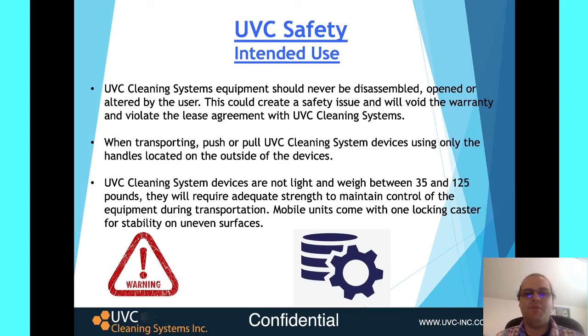UVC cleaning systems equipment should never be disassembled, opened, or altered by the user. This could cause a safety issue and will void the warranty and violate the lease agreement of UVC cleaning systems products. When transporting, push or pull UVC cleaning systems with only the handles located on the outside of the devices. And always remember that a lot of our devices weigh between 35 and 125 pounds, and they will require adequate strength to maintain control of the equipment during transportation. Our mobile units do come with a caster with locking abilities, so that you can place it safely on uneven surfaces.